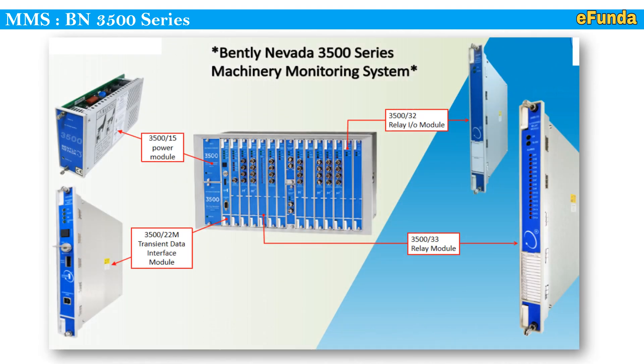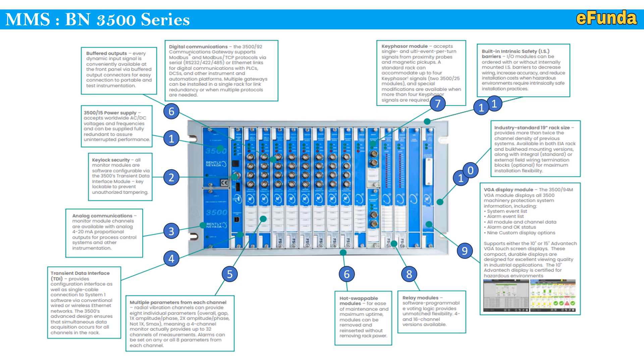Moving on to machine monitoring system — Bently Nevada 3500 series. One can refer to the picture where the Bently Nevada 3500 series machine monitoring system is shown with the complete rack. Some of the components include the 3500/15 power supply module, 3500/22M transient data interface module, 3500/32 relay I/O module, and 3500/33 relay module — these are the typical main components of the Bently Nevada monitoring system.